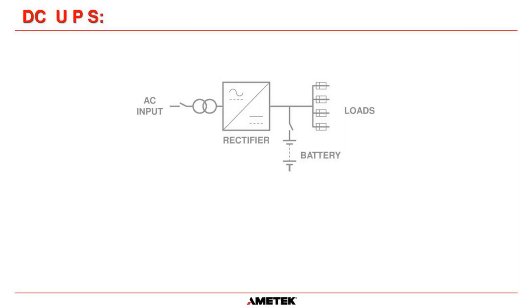So you can see on the left-hand side, we have the AC input. That's usually for industrial systems, three-phase 480 volts AC. Then we have our AC input breaker that goes into a transformer. And then we have our conversion stage here. We convert the AC into DC. Now, AMETEK Solidstate Controls uses SCR bridges, silicon controlled rectifiers. So that's our design. We then have a battery disconnect, and that then goes to our battery, and eventually you have your load circuits here. Okay, so that's just a very, very general overview of a DC system.